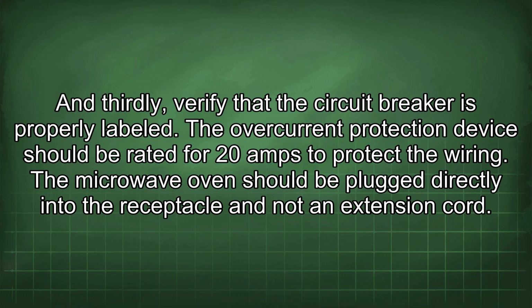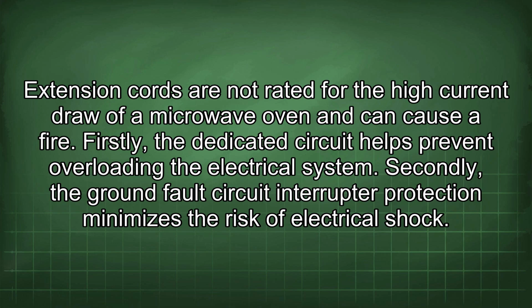The overcurrent protection device should be rated for 20 amps to protect the wiring. The microwave oven should be plugged directly into the receptacle and not an extension cord. Extension cords are not rated for the high current draw of a microwave oven and can cause a fire. Firstly, the dedicated circuit helps prevent overloading the electrical system. Secondly, the ground fault circuit interrupter protection minimizes the risk of electrical shock.